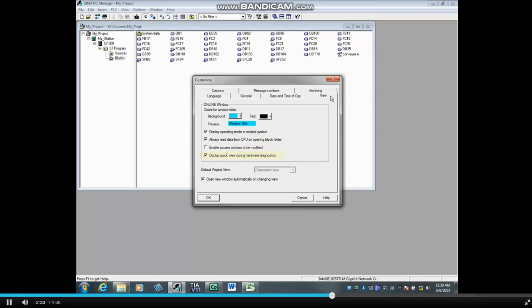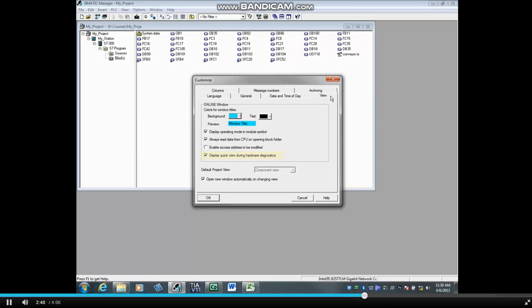Display Quick View during the Hardware Diagnostics is checked by default. This shows only the PLC and module faults with brief information when Hardware Diagnostics is launched from the Diagnostics setting choice of the PLC menu. Unchecking this box will give more detailed information in the Hardware Diagnostics window, but takes longer to load the information.